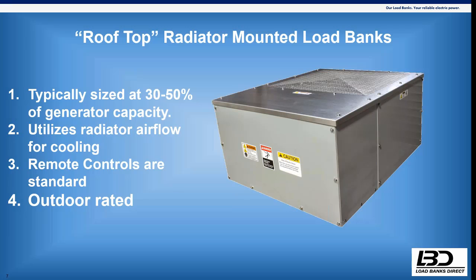I don't know, Martin, what do you think? Heat's always a problem in all load banks, though. Heat is always a problem. When people say, hey, I have a 1,000 kW genset, I'm just using round numbers, can we put a 750 kW load bank on there? We say, well, we don't really recommend it. Can we do 500 or 600 kW?